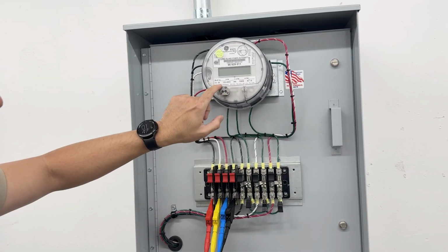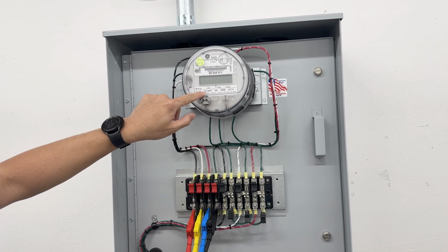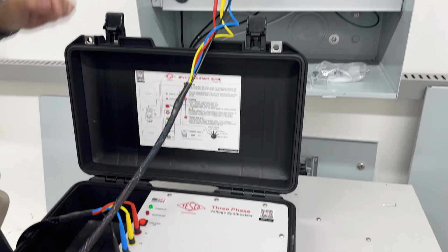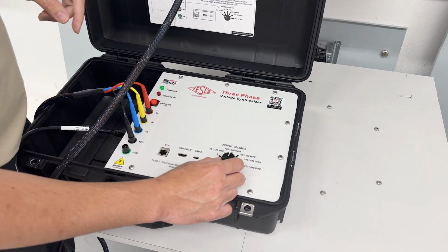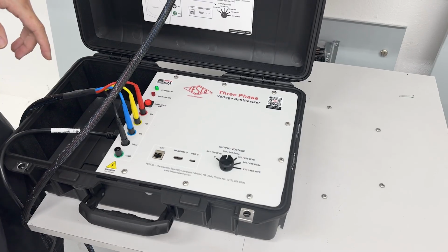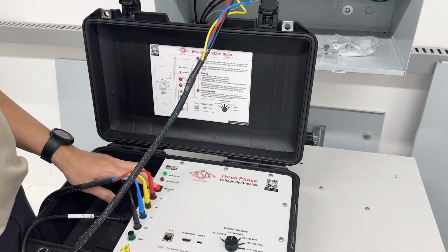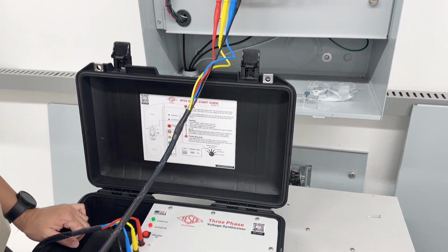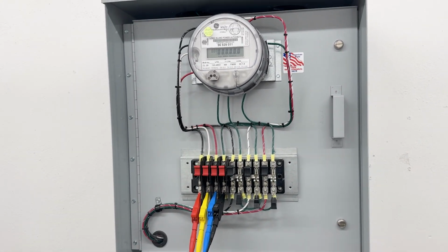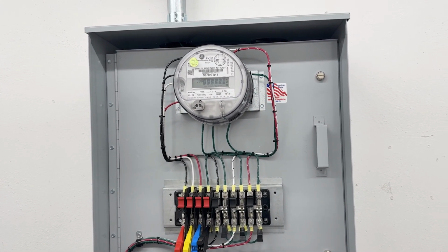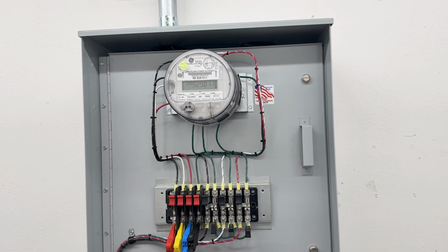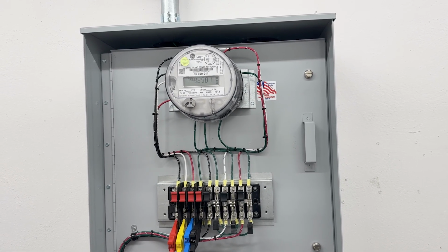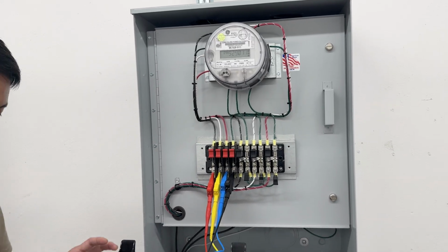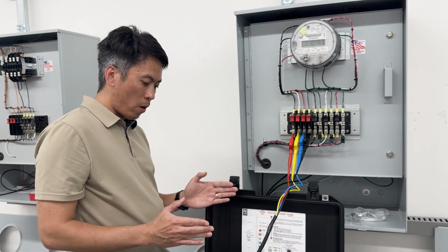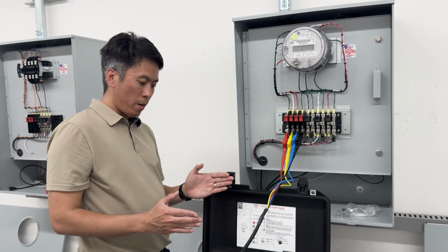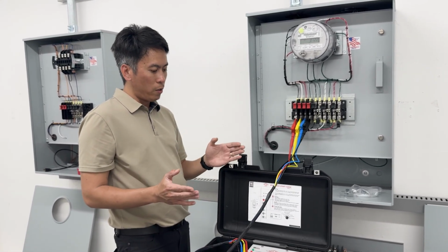The voltage it can go to is 120 to 480 volts, and we're gonna select the voltage through the rotary switch. In this case, I'm gonna use 120 240, and I'm gonna turn on the button. I'm gonna press that button there. And as you can see, it's powering up the meter. That's really it. So this is a three-phase voltage source. Each phase is capable of generating 100 VA per phase. That means it's line to neutral.